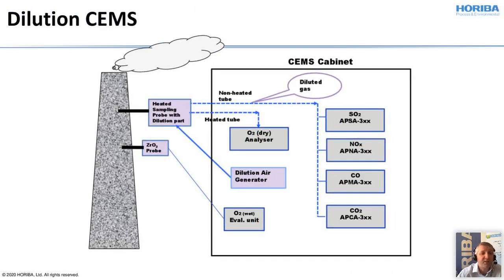What we have here is a picture. You see the stack with the heated sample line, and then you bring the gas to all the analyzers with a non-heated tube for the monitoring of, for example, SO2, NOx, CO, CO2. What we can't do is dilution for oxygen. The diluted sample cannot give the oxygen level in the gas, because it is diluted with more or less ambient air. So the measured oxygen is much higher than the real value of oxygen in the gas. That means finally we need to bring the gas in a heated line to an oxygen analyzer.